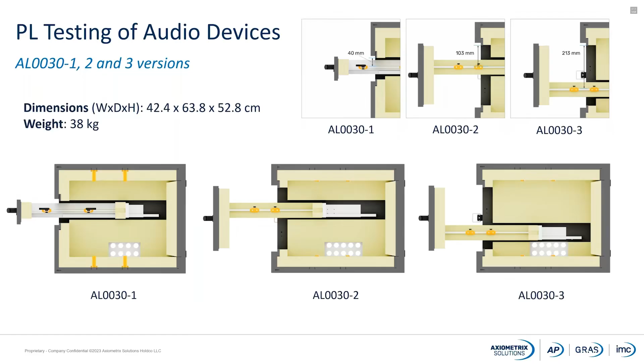You've probably seen in other pictures that on the side of the AL30, we have a connector panel. This connector panel will act as an interface between the inside of the chamber, where we have our device under test, and the outside of the chamber, where we have our analyzer or data acquisition system.